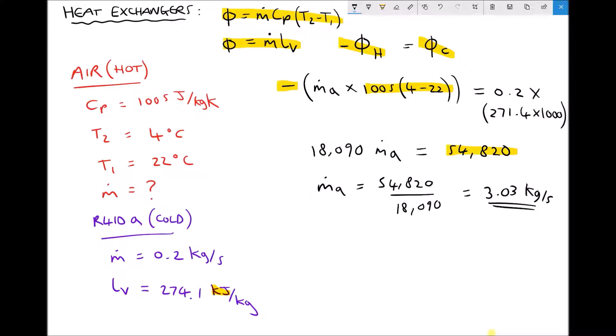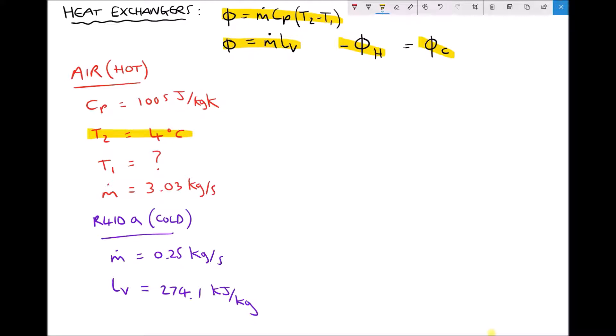Next we change a couple of parameters. At full capacity, the refrigeration unit can handle more than 0.2 kilograms per second of refrigerant — specifically 0.25 kilograms per second. We keep the mass flow rate of air at 3.03 kilograms per second (just calculated) and fix the outlet air temperature at 4°C. The unknown now is the maximum inlet temperature of air into the refrigeration unit in order to still achieve the desired outlet temperature.